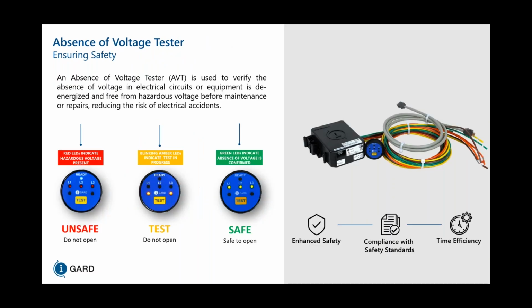Now, an absence of voltage tester is used to verify the absence of voltage in electrical circuits during a lockout tagout, where the equipment is de-energized and free from hazardous voltage before maintenance or repairs. This will reduce the risk of electrical accidents, which typically occur due to human error or device errors when it comes to voltage testing. Red LEDs would indicate that hazardous voltage is present, amber LEDs indicate that the test is in progress, and green LEDs indicate that absence of voltage is in fact confirmed. This approach actually uses 2 wires per phase as well as 2 wires for ground, in comparison to the 1 wire that appears for voltage indicators as well as voltage test ports.